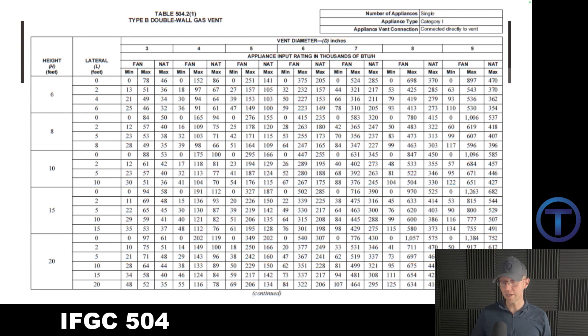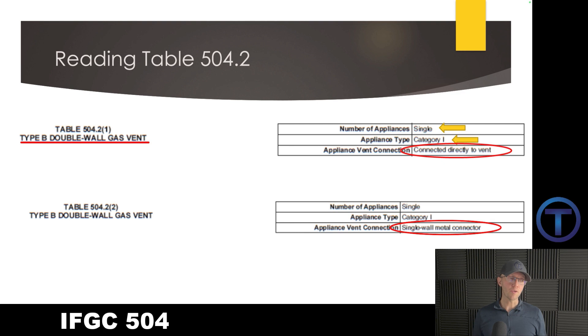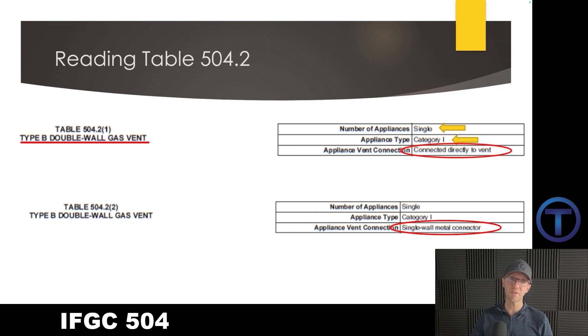Let's talk through what information you need to know. Look at the top of these tables — this is the same as with gas pipe sizing. First of all, you've got to know the type of vent that you're dealing with. Most of the first tables here are the type B double wall gas vent. It says it right at the top. So right off the bat, I know I'm going to use a draft vent, type B, going out of the building. But then there's other information I need to know.